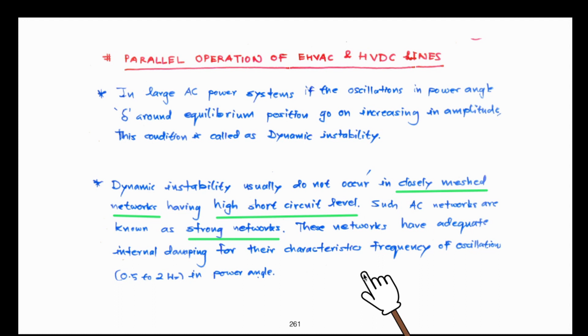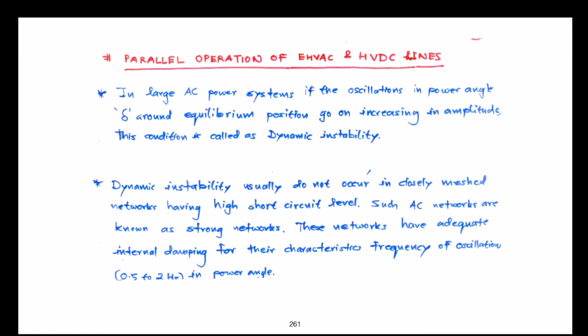But what will happen if the AC networks which are interconnected are not very strong networks? If two or more AC networks are interconnected and one of them, or maybe both of them, are not strong AC networks, in that case the power angle oscillations may lead to generators falling out of step or pulling out of generation, leading to consequences which can ultimately lead to major breakdowns or cascade breakdowns, a failure of the grid, and so on. Right? So, what can be done? The option is to have parallel connected HVDC links.